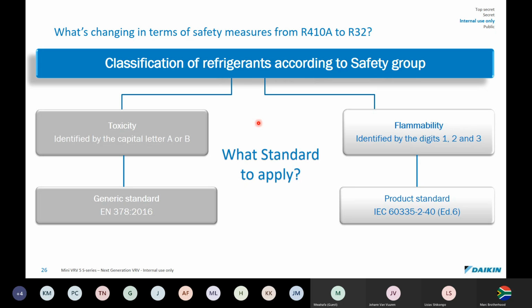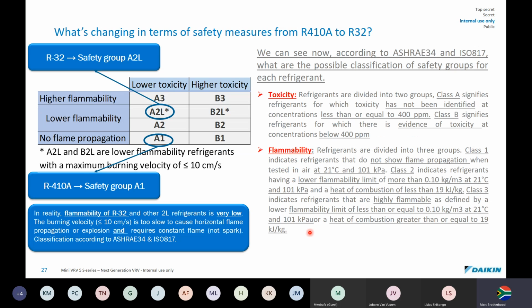So, yeah, classification of refrigerants according to safety groups. Refrigerants are toxic. Not that you breathe them in and you're going to lie on the floor choking to death. They're toxic in the sense that they asphyxiate you. They cut off your oxygen supply to your brain. It's not that you breathe it in and it tastes very bitter and all of that stuff. So we label refrigerants depending on how toxic they are with an A or B, and also how easily they burn when you bring them in the presence of an ignition source. So you have digits 1, 2, and 3, and letters for toxicity. And here you can see we used IEC 60335 and EN. So there's two standards Daikin have used.